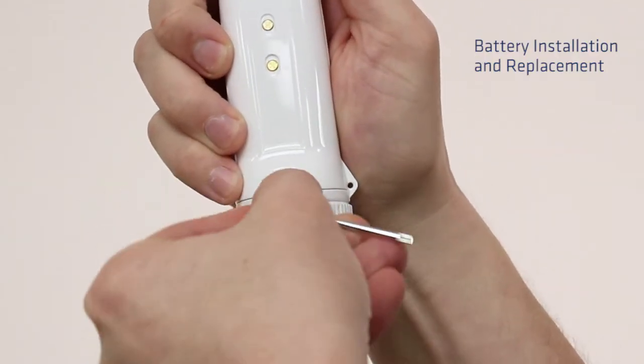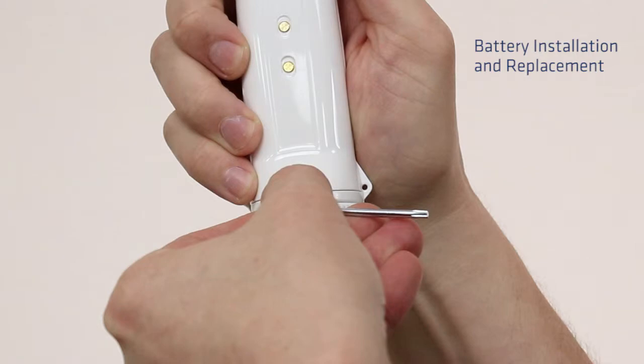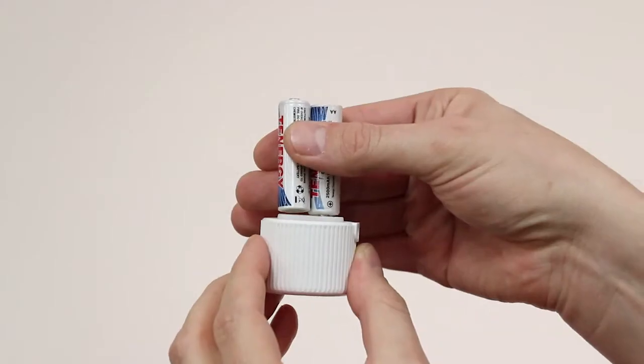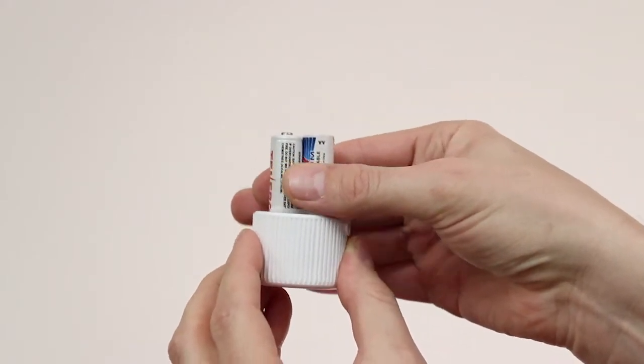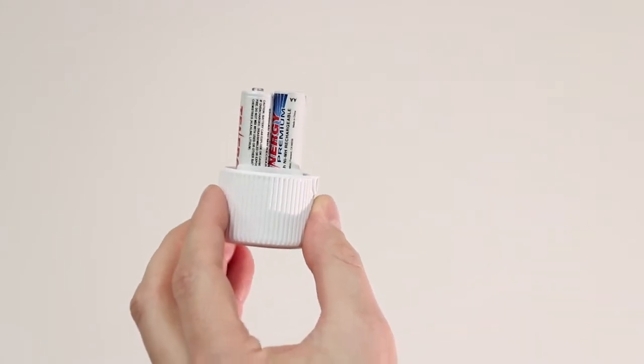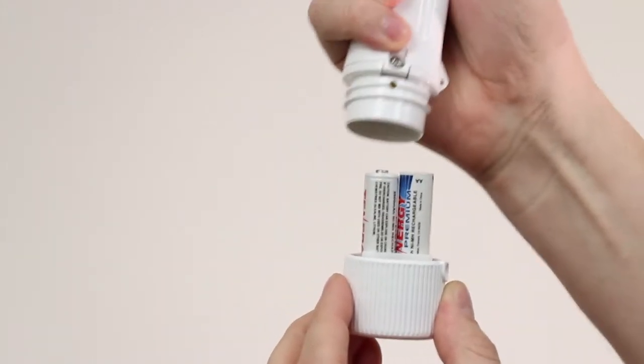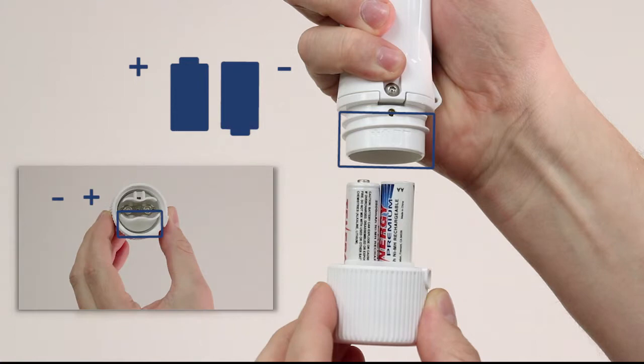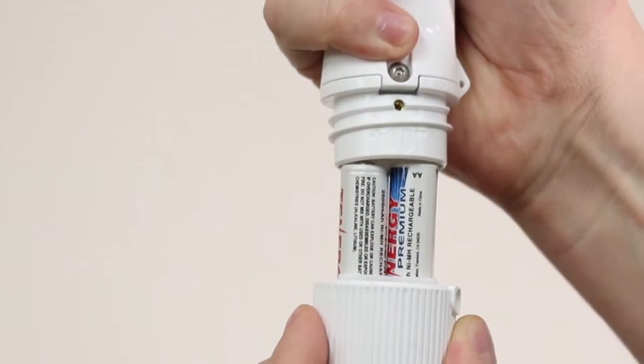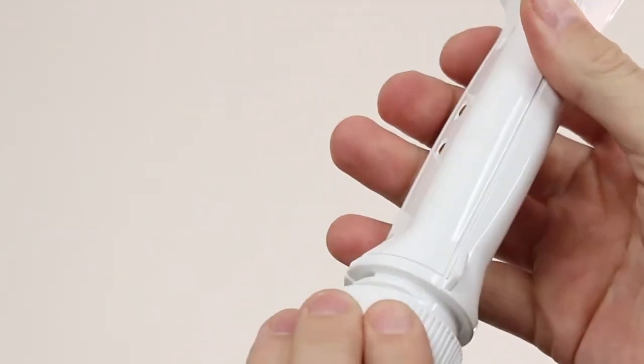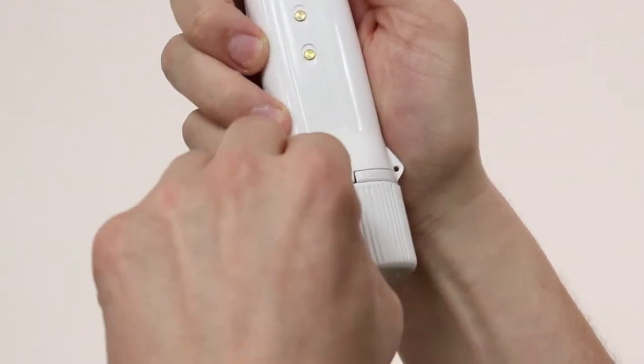Remove the locking screw from the cap of the battery compartment using the Torx T10 tool provided with the kit. Load the batteries, respecting their polarity, into the cap of the battery compartment. Place the cap back into the device and secure it by tightening the locking screw.